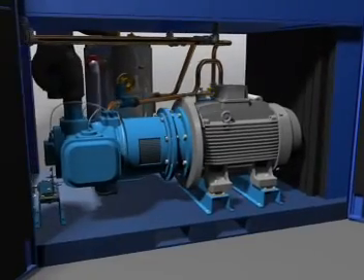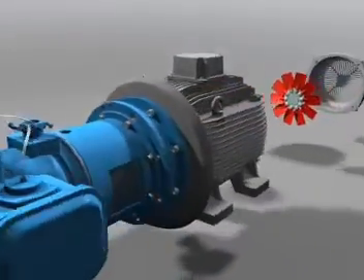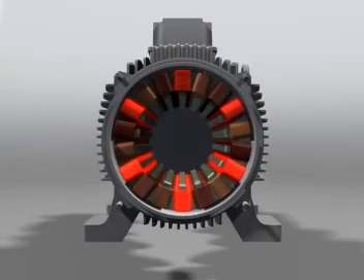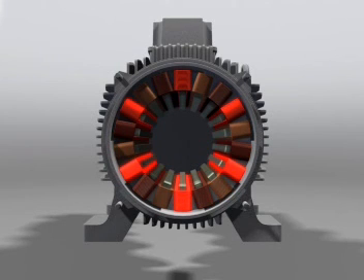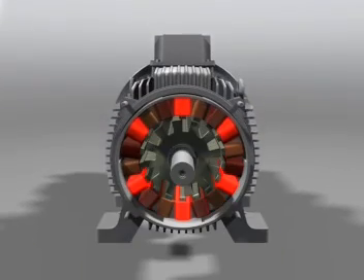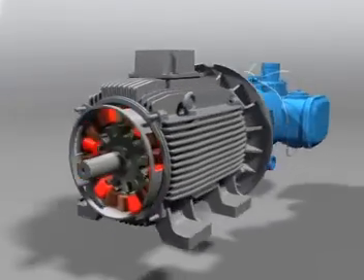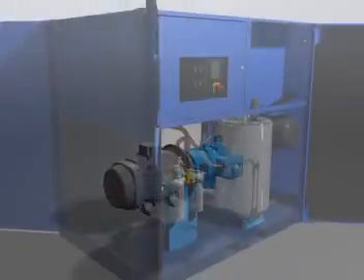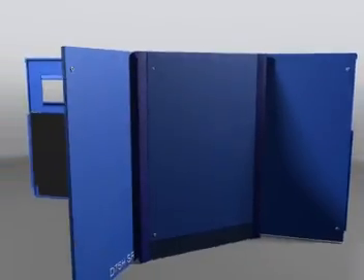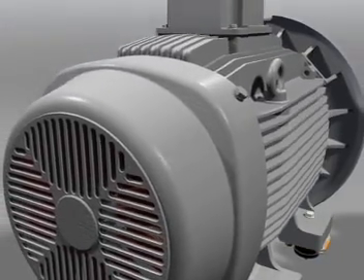The compressors can be driven by a fixed-speed motor, an inverter, or by our innovative switched reluctance drive system. Using the SR drive system, the digitally controlled three-phase motor enables the speed of the motor and thus the volume flow of the compressor to be precisely controlled to meet your changing demands. Fine pressure control ensures that you use exactly the energy required to do the job and no more. The technology gives you soft starting and stopping of the main drive motor, reducing the stresses on mechanical and electrical components. We've taken our outstanding SR technology and improved it.